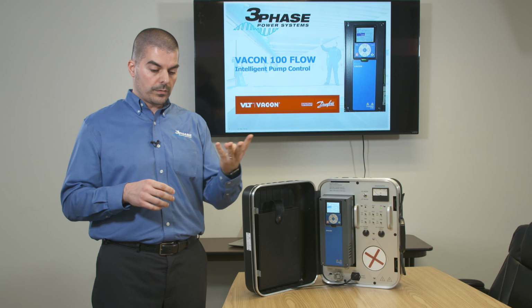Beautiful, beautiful. The other thing is if a drive is traditionally operated by a PLC, the PLC may fail. And traditionally what is being done with PLCs is they tell the drive to run at a predetermined speed if the PLC, the main computer, fails. So this drive, the 100 flow, has a potential of having its own PID controller directly inside.